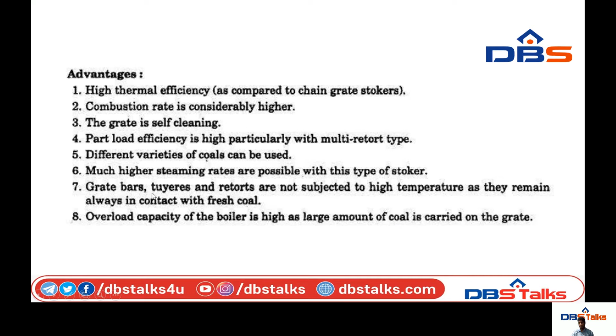The grate is self-cleaning. The main advantage of this type is that it is self-cleaning, which makes cleaning the grate very easy, and different varieties of coals can be used. Next, the overload capacity of the boiler is high, as a large amount of coal is carried on the grate.